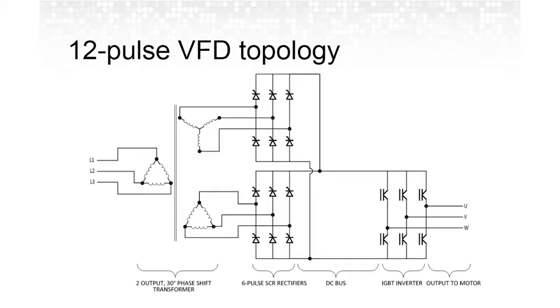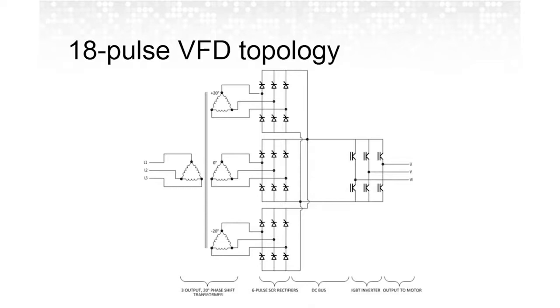And while we were saying that the 6-pulse VFDs are relatively small, you can wall mount them in most cases, most 12-pulse VFDs are freestanding enclosures. And in addition, they're also slightly less efficient than 6-pulse VFDs.